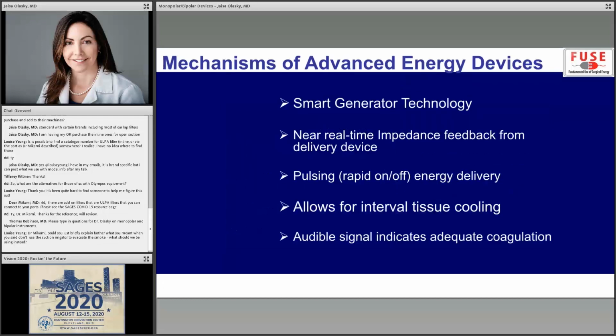A few things about the mechanism. Keep in mind, these advanced bipolars have really smart technology. I like to say it's smarter than we are, because it is. You should learn the audible signal that is telling you there's adequate coagulation. You don't need to double seal anything. This device is telling you because it's measuring the tissue between the jaws. And it's going to be right more often than we are in terms of that you're done.